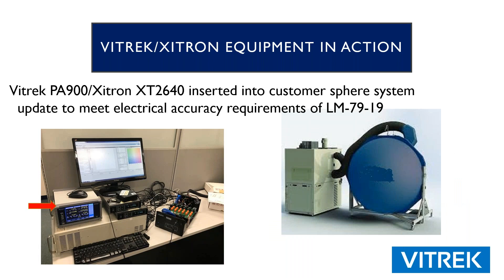Here is a picture of the Vitrek PA900 — or Xitron XT2640, indicated with the red arrow — inserted into a customer's sphere system, updated to meet the electrical accuracy requirements included in LM79-19. This particular customer was previously using the legacy Xitron 2801 power analyzer, which according to LM79-19 is no longer accurate enough for those types of measurements. This shows our meter being used in a real customer environment.